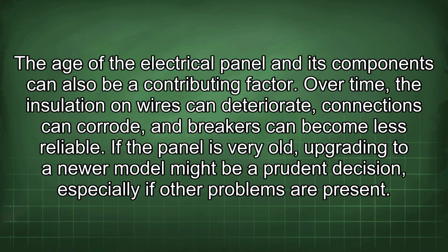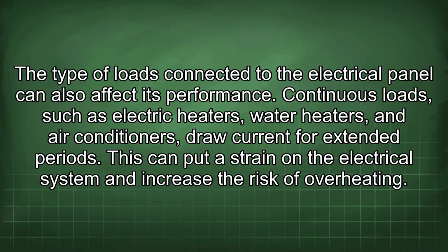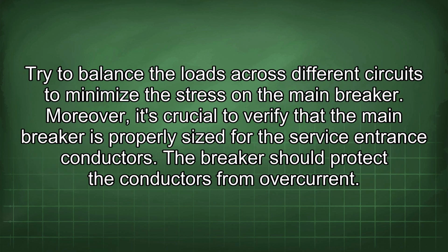If the panel is very old, upgrading to a newer model might be a prudent decision, especially if other problems are present. The type of loads connected to the electrical panel can also affect its performance. Continuous loads, such as electric heaters, water heaters, and air conditioners, draw current for extended periods. This can put a strain on the electrical system and increase the risk of overheating. Try to balance the loads across different circuits to minimize the stress on the main breaker.